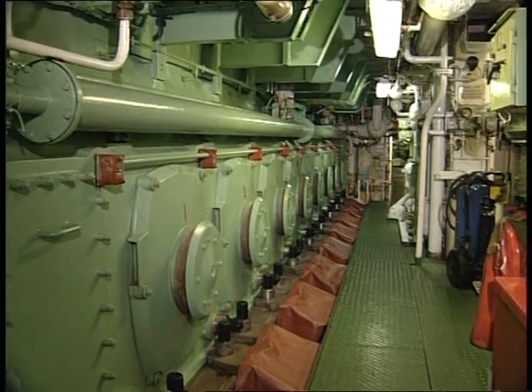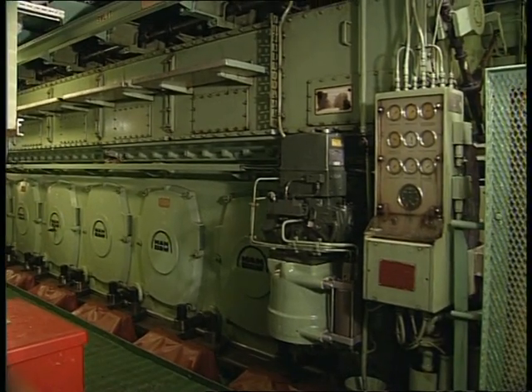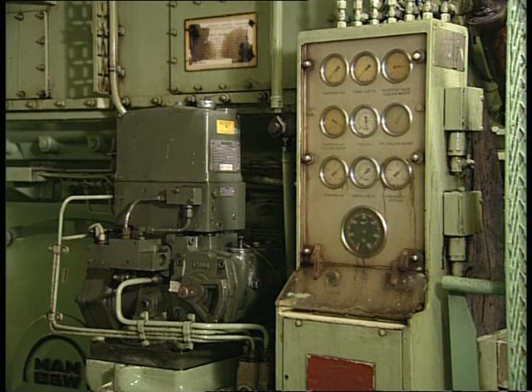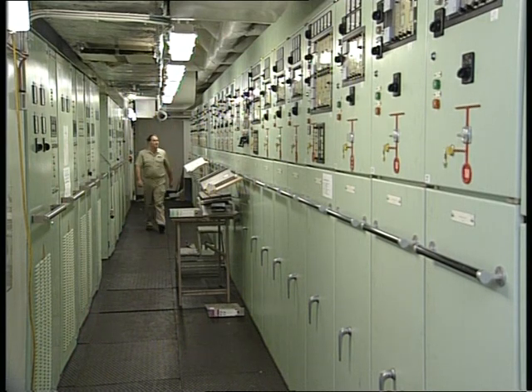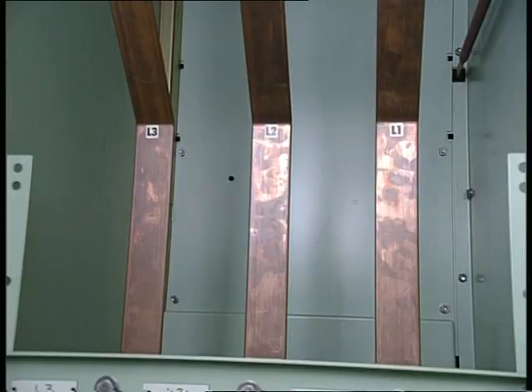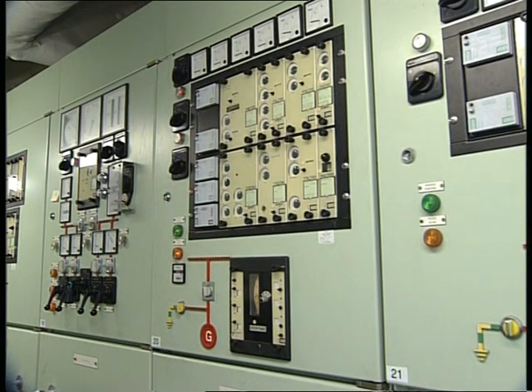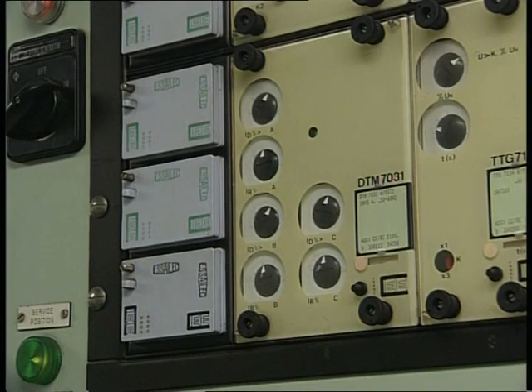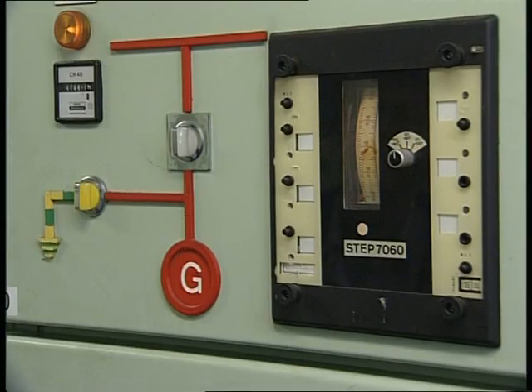Power generation starts with the diesels. Each diesel engine has its fuel input regulated by a Woodward electronic governor to maintain constant speed in order to obtain constant generator frequency of 60 hertz. The main 6.6 kV switchboard will be separate from the engine control room. Here are the 6.6 kV busbars and the main protection relays. These protection relays continuously monitor critical operation levels such as currents, voltages, earth leakage, unbalanced loading and temperatures, and where necessary give an alarm and trip a main circuit breaker. The breakers will be of the air type, the more modern SF6 gas-filled type, or even the vacuum interrupter type.